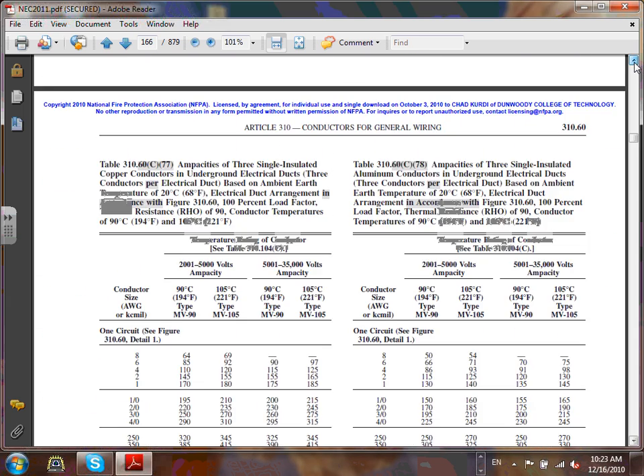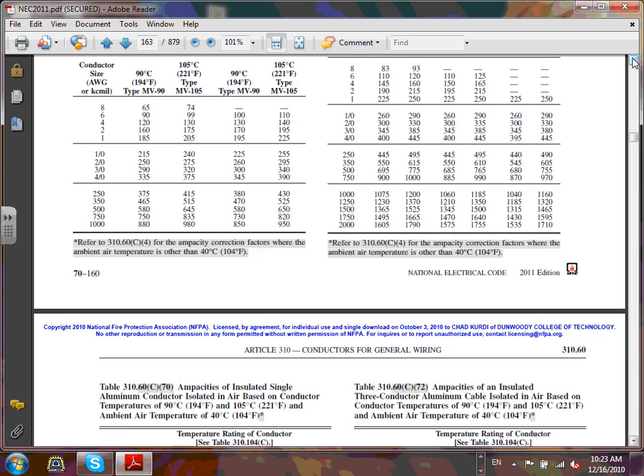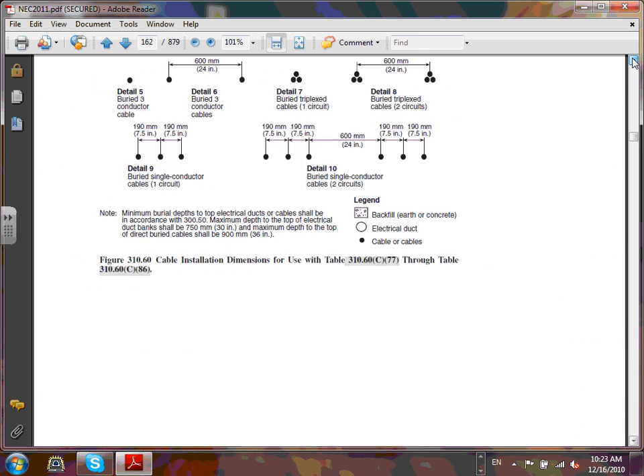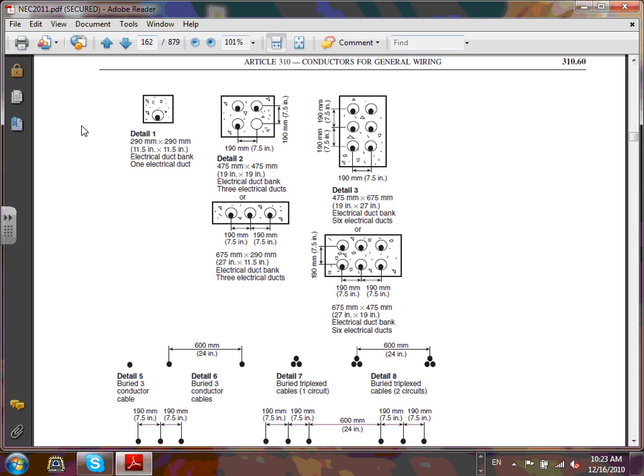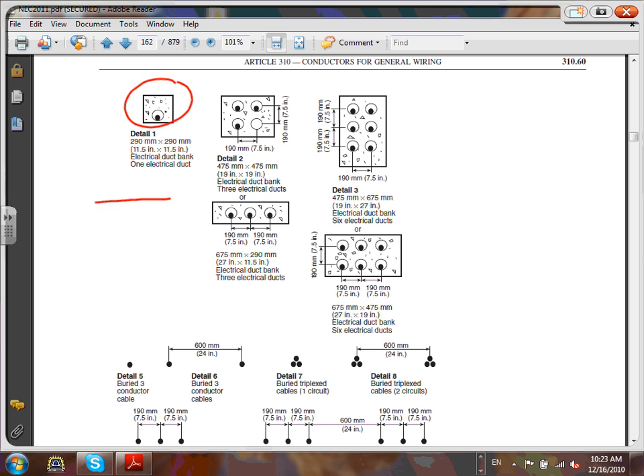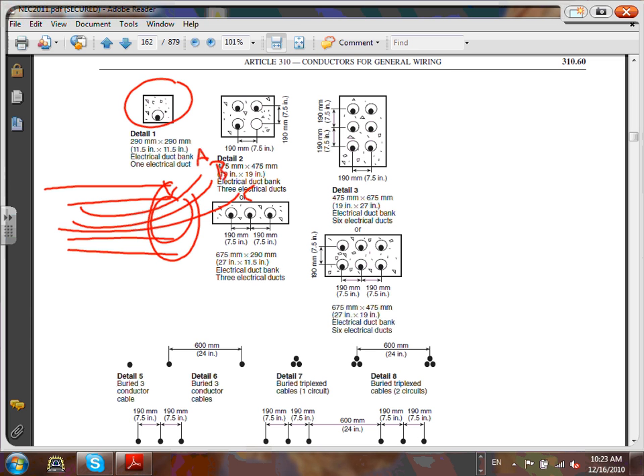I want to bring to your attention the details. Come on, Chad, since I have a few minutes here to bug you. If you guys look at the detail here, it says detail number one. Detail number one is a multi-conductor cable. That's what we used. This guy here is basically a multi-conductor cable. What is a multi-conductor cable, Chad? Here's 1, here's 2, here's 3, phase A, phase B, phase C, and if it's a medium voltage, you're going to find it's really weird because medium voltage, it's thick insulation. Here's my multi-conductor cable. I decided single-handedly to use a medium voltage multi-conductor cable.